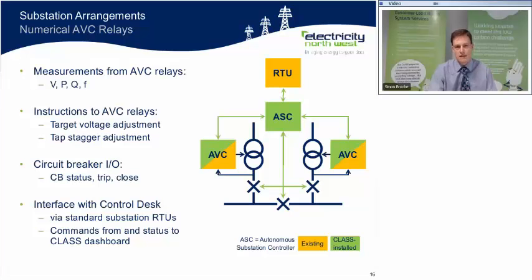The AVC relays, we've used a mixture of existing relays, and in some circumstances for some substations we have installed new AVC relays. And the ASC needs to issue instructions to these AVC relays to adjust the target voltage and also to carry out the tap stagger. And it receives measurements from the AVC relays of voltage, of real and reactive power, and of frequency. The final area of communication within the substation is from the ASC to the circuit breakers. So it receives the circuit breaker status, and it can issue trip and close commands to the circuit breakers, although in this project, only trip commands are issued.